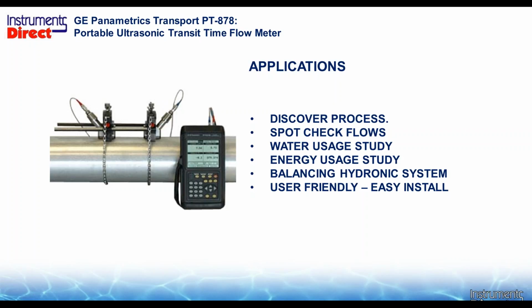Maybe you want to put meters throughout your facility. What's the flow rate? Well, walk through the plant and use your portable flow meter, conduct the survey, add the temperature sensors to it, do a BTU study. Portable flow meters on the outside of the pipe can save you tons of money. There are no holes in the pipe. There's no prep work, no drilling or anything like that. You're a self-contained unit. You're all set to go.